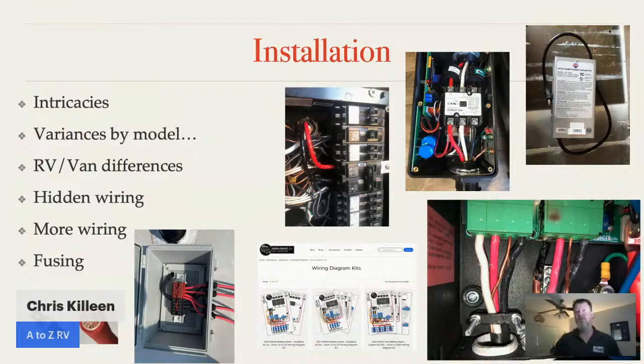This is a Victron Multiplus 2 installation gone wrong, and definitely one that a lot of the distributors have seen when installations aren't done all the way up to spec. That white line, the neutral, is going into the far left-hand side of both of those green terminal blocks. But the one on the right that's all burned up didn't get enough stripped off of it.